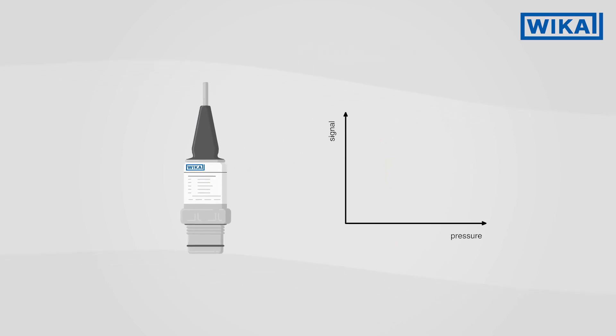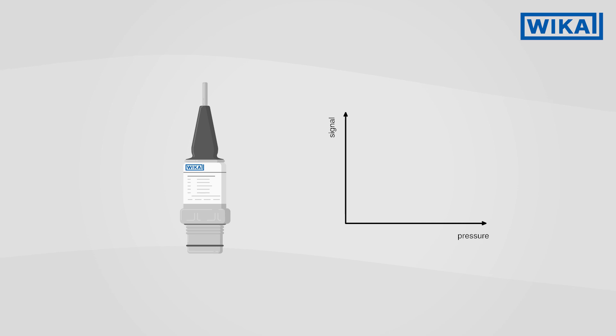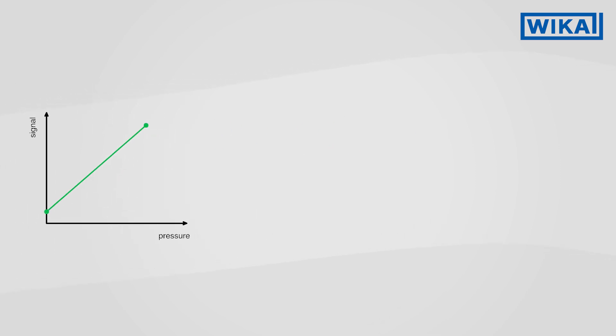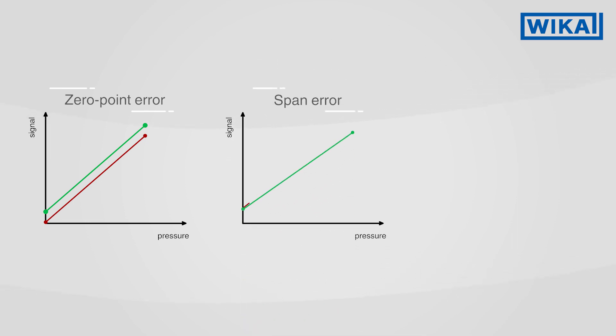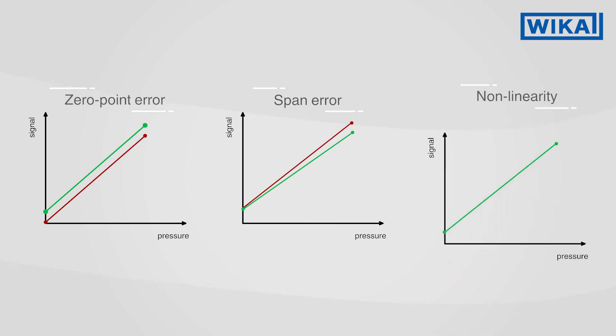How do the three errors just described affect the measuring process and the pressure sensor? The sensor characteristic curve describes at how much pressure which output signal is issued. The zero point error shifts the sensor characteristic curve in parallel, the span error affects the slope of the straight line, and non-linearity turns the line into a curve.